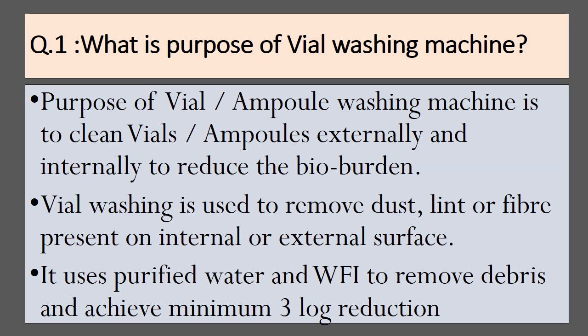The purpose of a vial or ampoule washing machine is to clean vials or ampoules externally and internally to reduce the bioburden. Vial washing is used to remove dust, lint, and fiber present on the internal or external surface. It uses purified water and WFI to remove debris and achieve a minimum 3-log reduction.